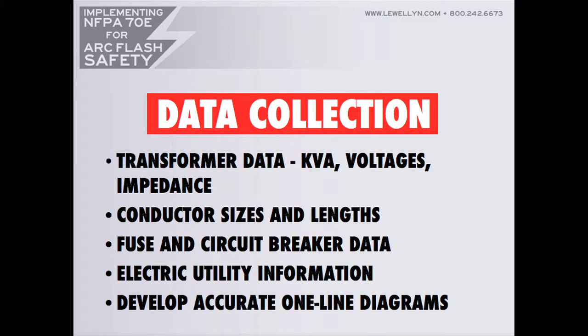Now, in data collection, we're going to collect transformer data. We're going to write down KVA and impedances, all kinds of stuff that only engineers could care about. We're going to write down conductor sizes coming out of that transformer going to your switchgear. We're going to open that switchgear and write down everything inside. Every wire size, everything connected to everything else, every part number, every accessory, every trip unit, every setting, hundreds of things in switchgear to write down. We'll write down all of it.